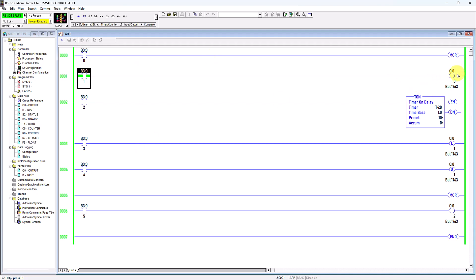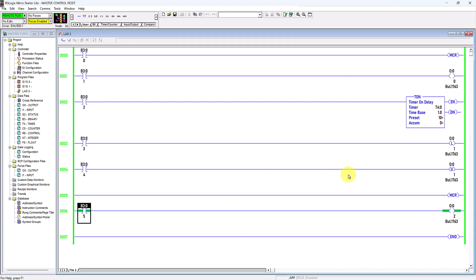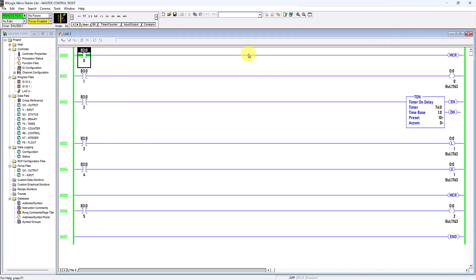If I trigger this to close, it has no effect because the MCR is not energized yet — it acts like an emergency switch. For a rung outside the fence zone, triggering it to close will energize the virtual output coil normally. Now let me toggle a bit — virtual power energizes the MCR, activating all rungs inside the control zone. Now if I toggle a bit on this one, I can turn it on.